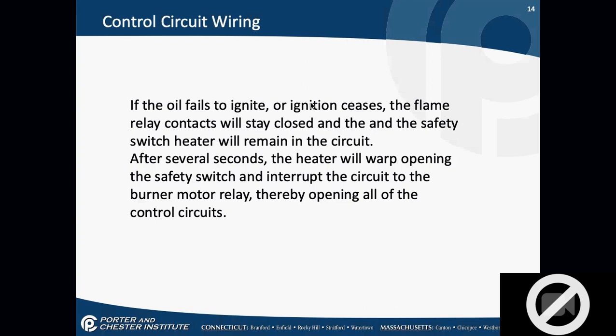After several seconds, the heater will start warping. Okay, it's bimetal. The safety switch is bimetal, and it interrupts the circuit to the burner motor relay, opens all of the controls, shuts everything down.